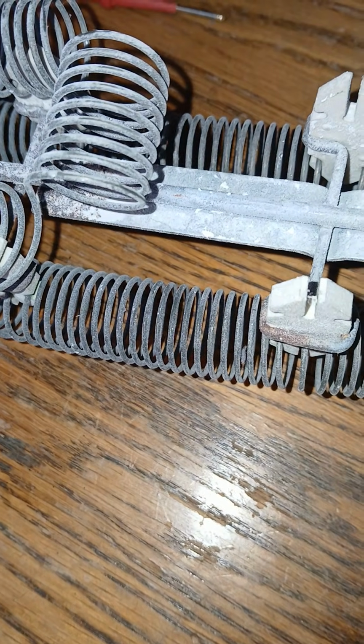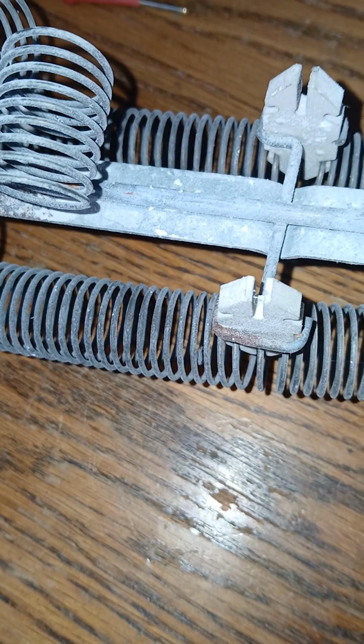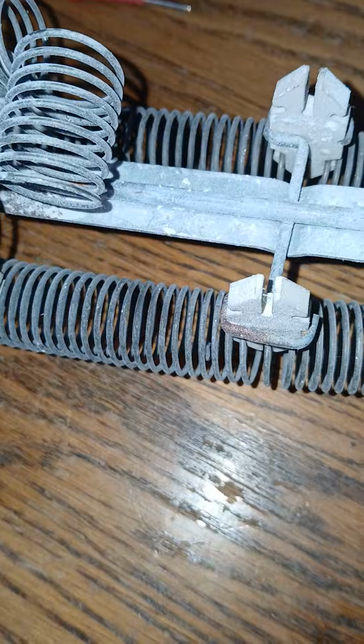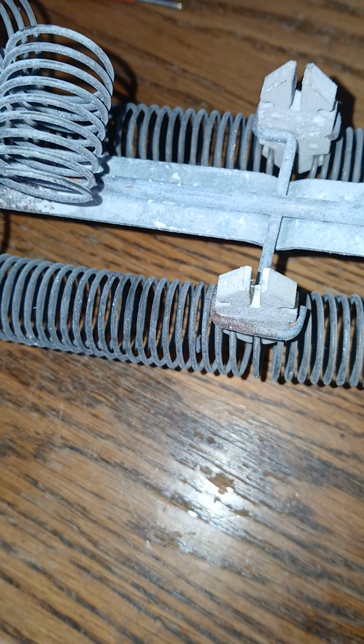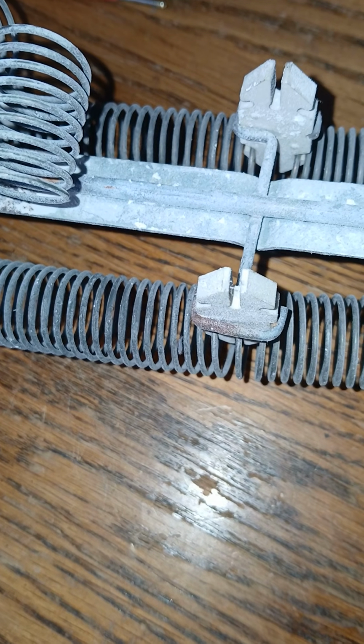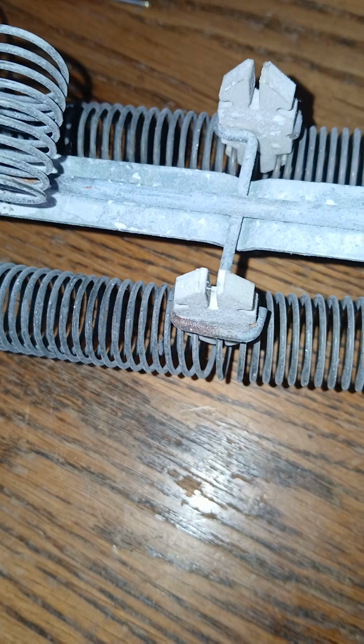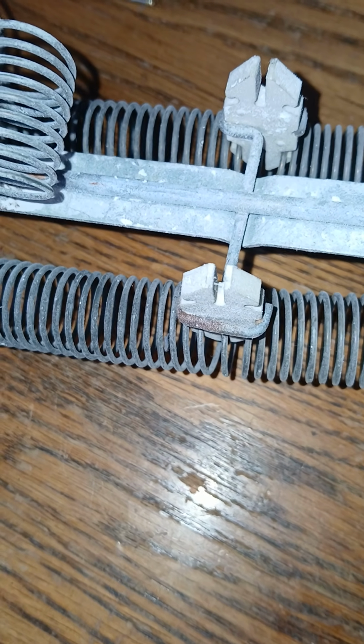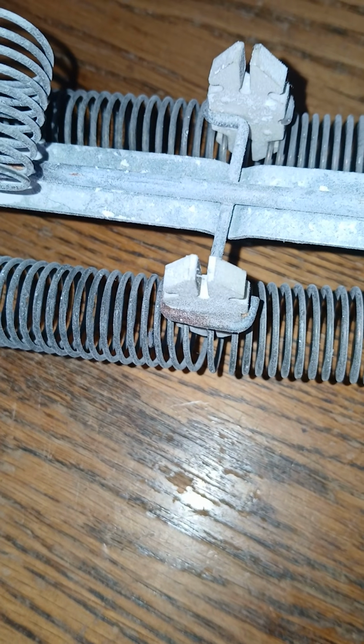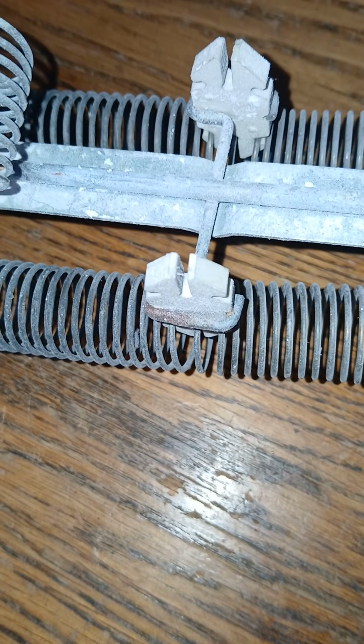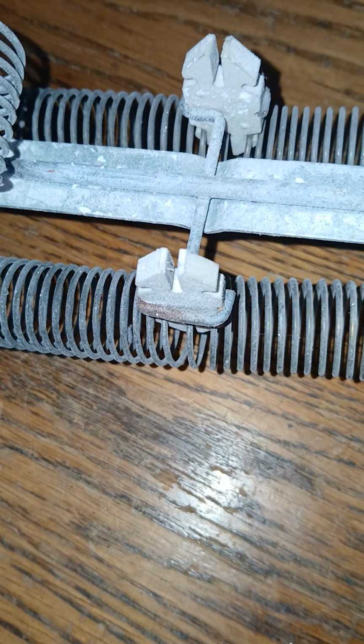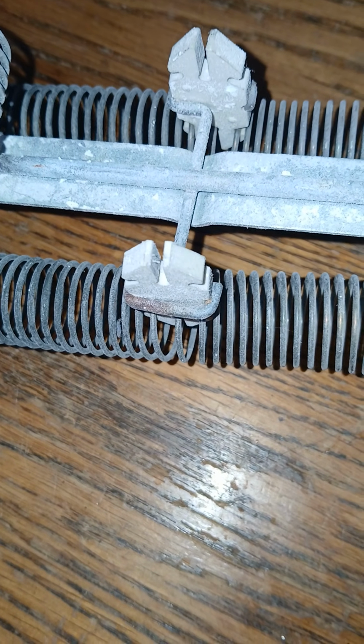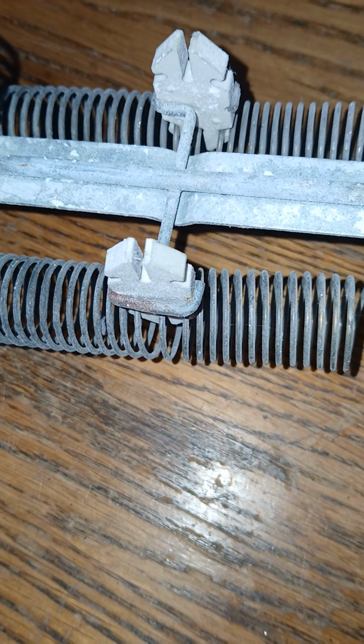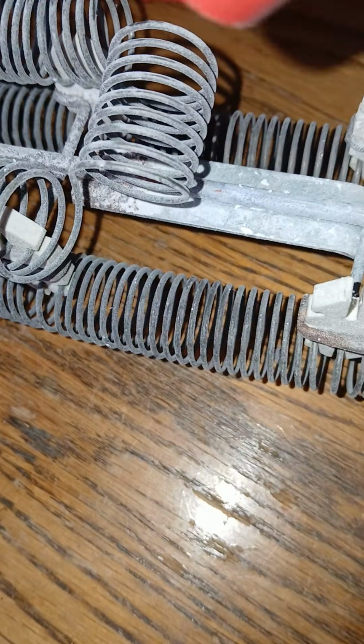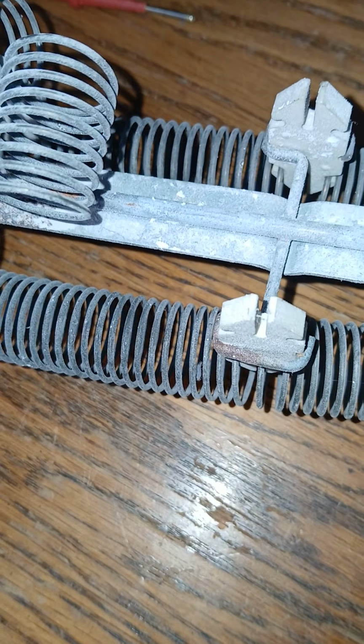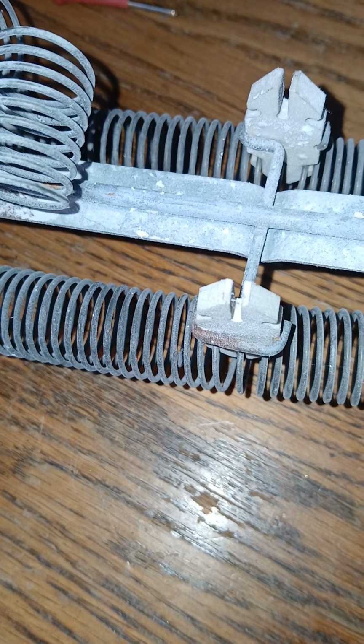At times the heat pump needs to go into defrost mode or emergency heat. If it's in defrost mode, some thermostats say AUX, auxiliary—like an auxiliary verb, it would be a helping, so it needs a little help. While it's doing this, it needs to heat these up and put some warm air into the house while going into defrost mode. If for some reason one needs emergency mode, they go to the thermostat and flip it to E. This locks out the condenser outside, and the heat strips here light up. One caveat: once these heat strips light up, the power bill does start to get a little higher.